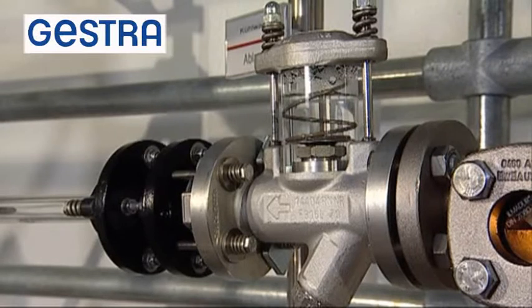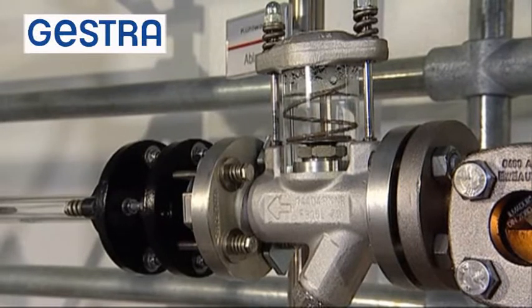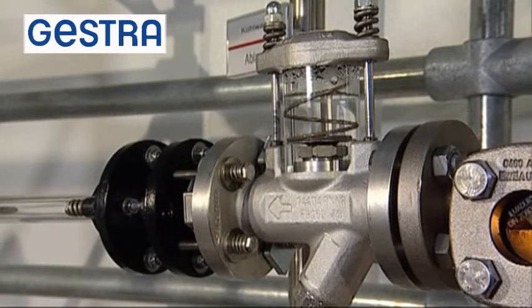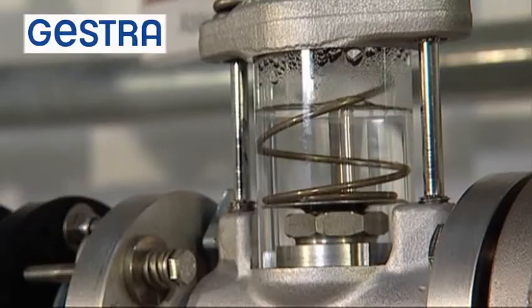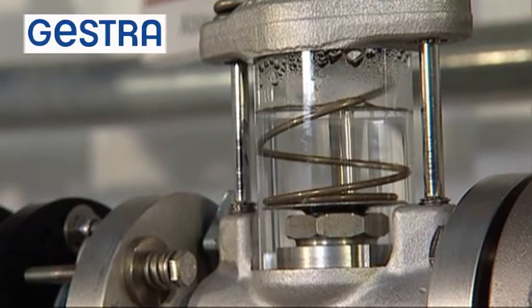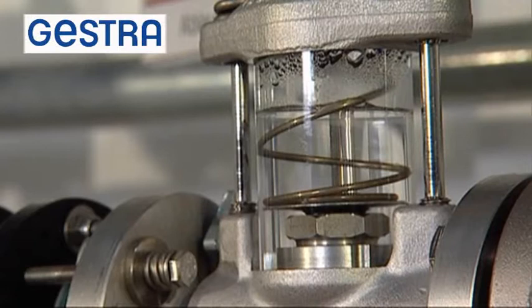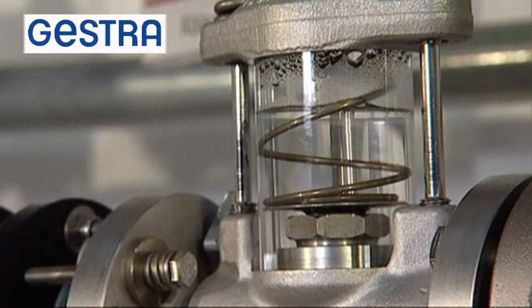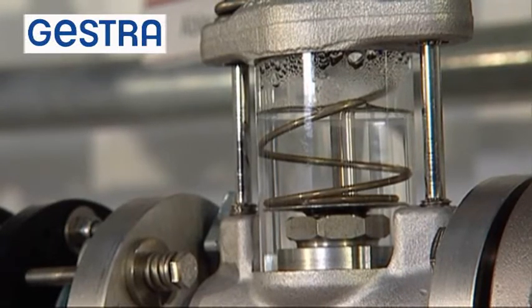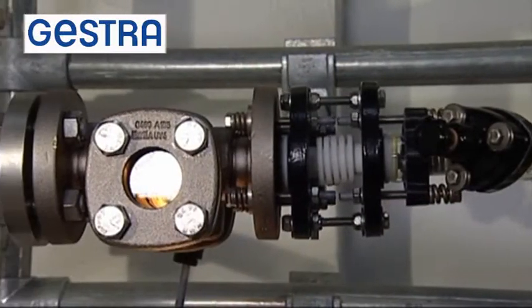Owing to the temperature difference between saturated steam and air, the membrane regulator detects whether there are any unwanted gases in the heating system. The GESTRA membrane regulator has the lowest undercooling in the world and is therefore frequently installed as a separate air venting unit in steam systems.